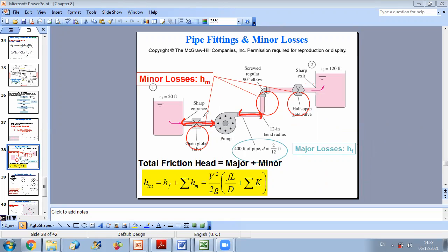And you can add together parts that have common characteristics, yani parts having common Reynolds and common epsilon over D. Then, if you want, they can be lumped together, because this can be written as f times sum of lengths over D. Again, I repeat, if the same characteristics of epsilon over D and Reynolds are satisfied.